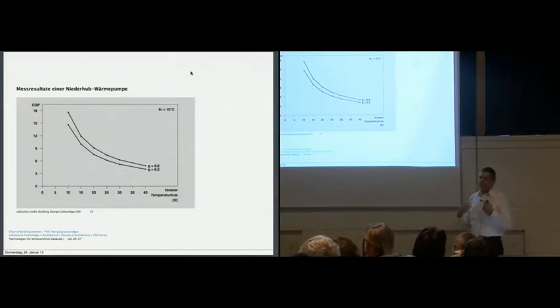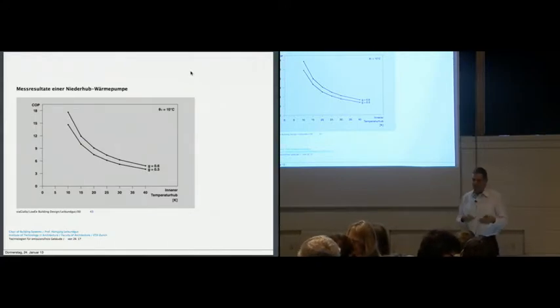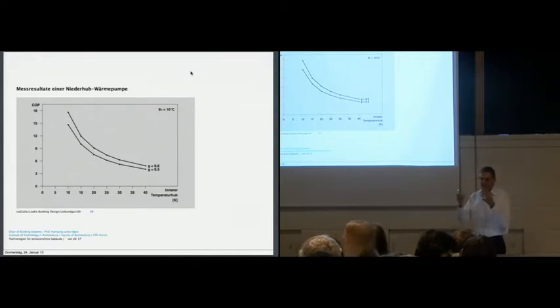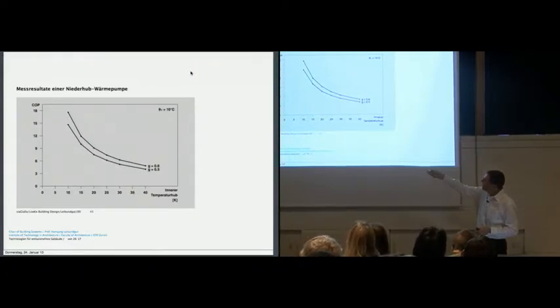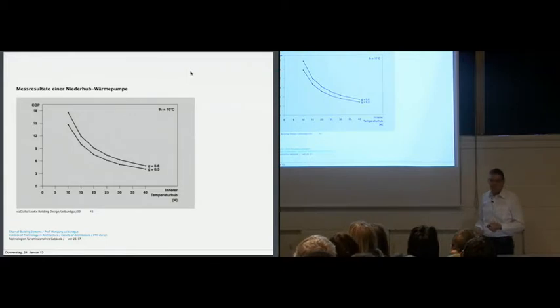Drilling down to 400 meters means we have one part of this temperature lift we decide on the site, the construction site and the regeneration, and the other part has to do with the heating system inside the building. The two together make this temperature difference, and we want to do it like this, bringing up the COP to 12. That's a normal machine with the internal coefficients of performance, that is the friction losses and compression losses and so on of the machine inside. There's a G value or zeta value of 0.5. We are able to produce a machine with 0.6 and bringing up in heating to 10 or 12. And that's what we're producing.